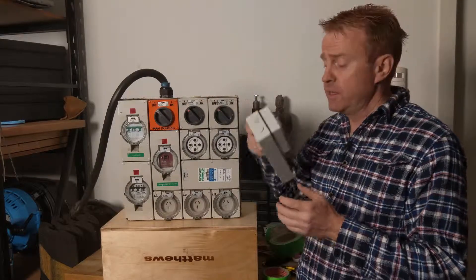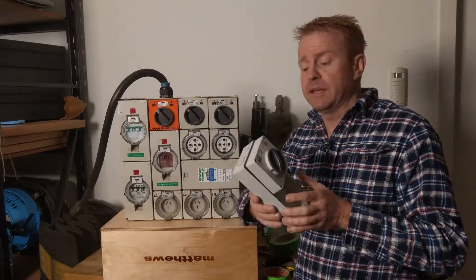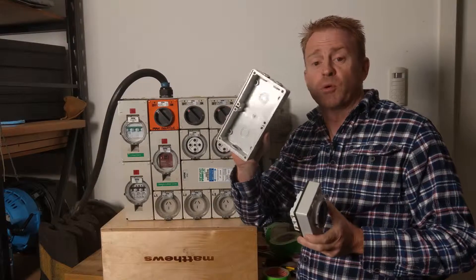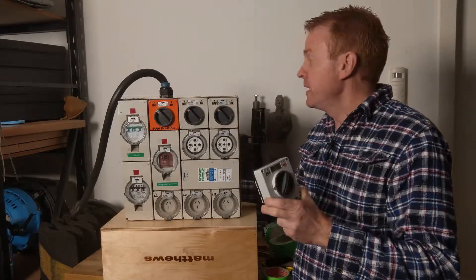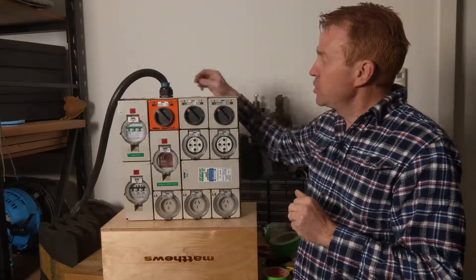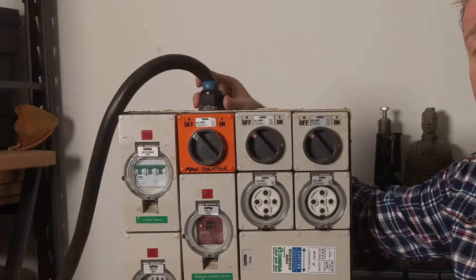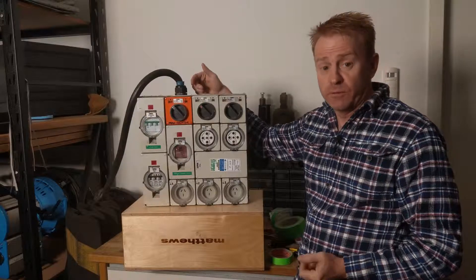So when you're doing your visual inspection check that the switch gear and the outlet are mounted to a waterproof enclosure. They're not mounted directly onto the wall. The other thing to check is where the power goes in. Make sure it's got a proper waterproof connection. It's not just a hole with silicon glue for example.